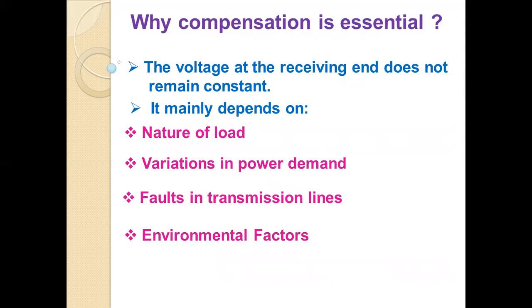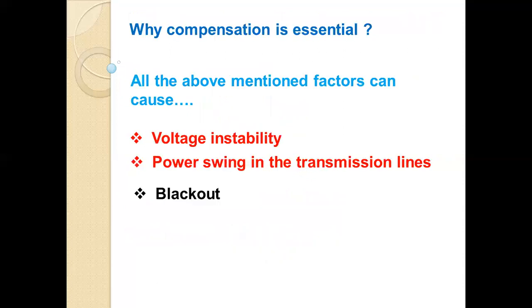Why is compensation essential? The voltage at the receiving end does not remain constant. It mainly depends on the nature of the load, variation in power demand, faults in the transmission line, and environmental factors. All the above-mentioned factors can cause voltage instability, power swings in the transmission line, and blackout.